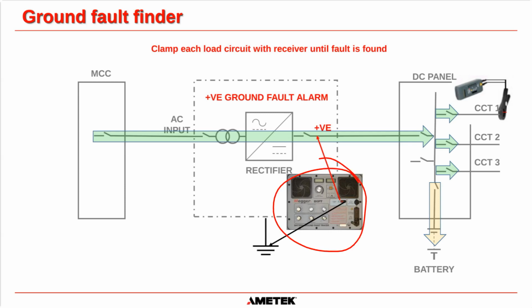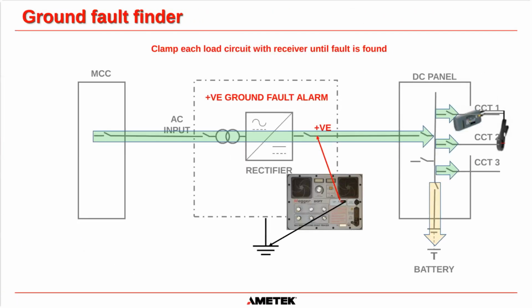So what you do is you get your CT and you put it on circuit one. Obviously, remember we're saying that the fault was on circuit three. So we put it on circuit one, and your receiver is going to tell you that there's no fault there. It won't pick up a signal, okay? So you put it on circuit one, no signal, everything's good. We then move that amp clamp down to circuit two. Once again, the receiver is going to tell you there is no signal coming back from the signal generator, so the fault is not on circuit two.